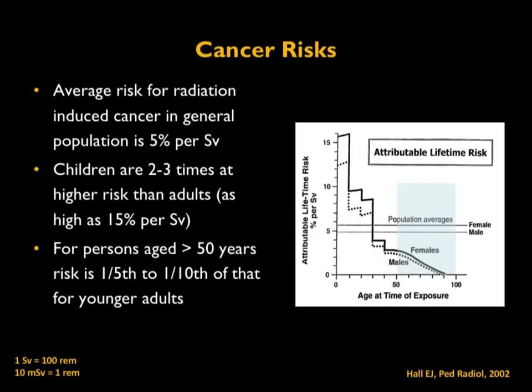One of the key risks is radiation-induced cancer risk. This graph shows attributable lifetime risk versus age at time of exposure. For most radiation protection purposes, we use a constant risk factor of 5% per sievert—noting that sievert is a very large quantity; in imaging we only talk about millisieverts, which is one-thousandth of a sievert. In reality, there is a slightly different effect for different age groups. Children are at 2 to 3 times higher risk than adults, while for persons older than 50, the risk is 1/5th to 1/10th of the adult risk. This is why the right word is to 'optimize' dose, not simply 'lower' it—the dose should be the right dose for the imaging to be done.